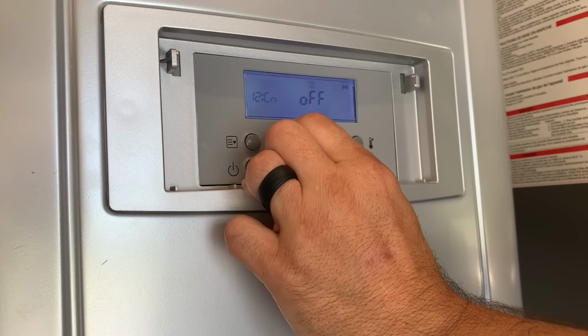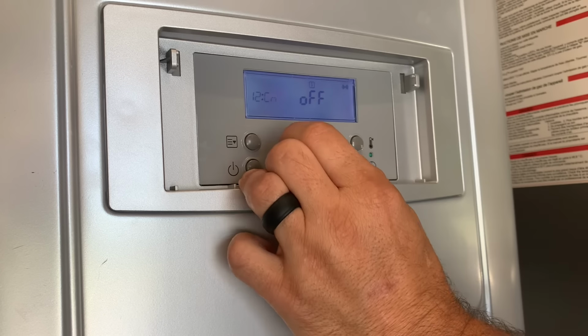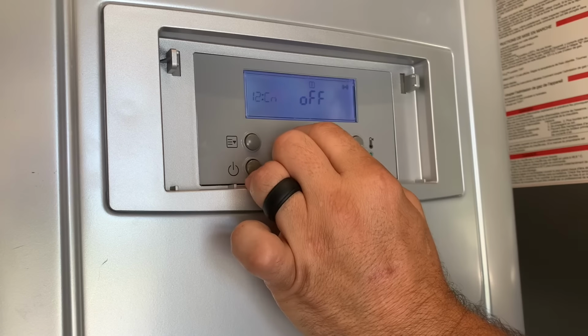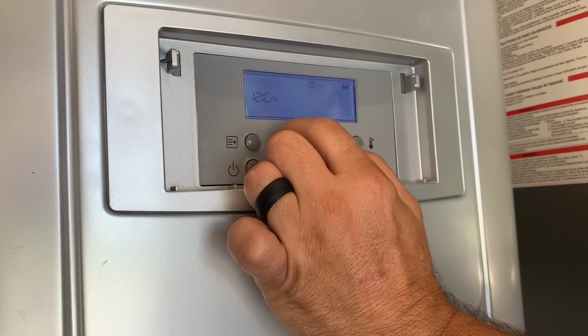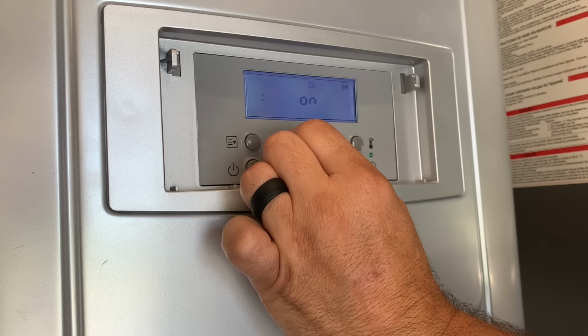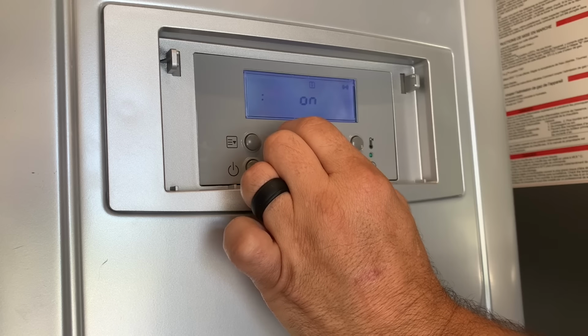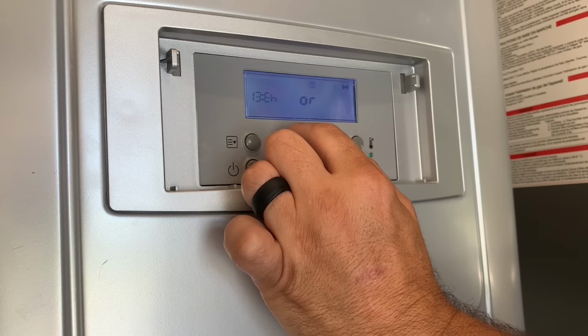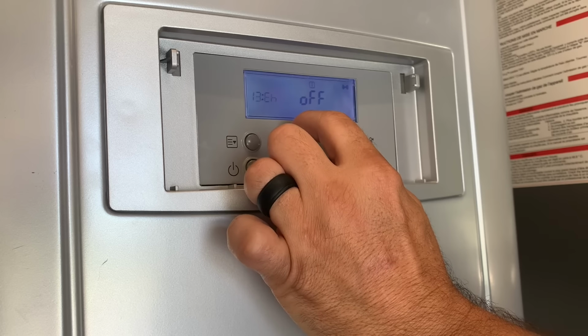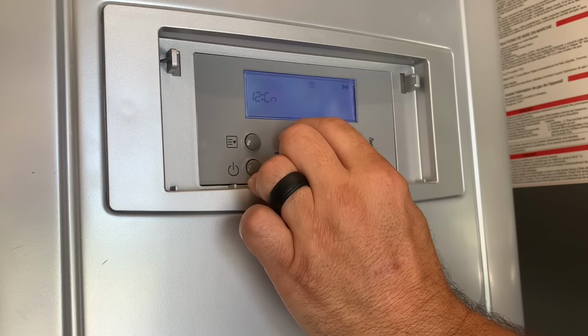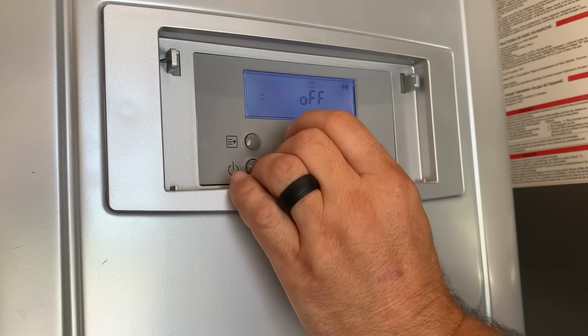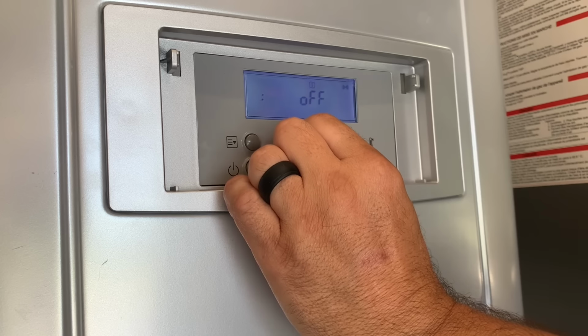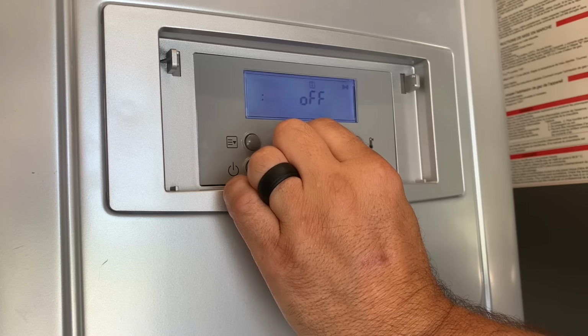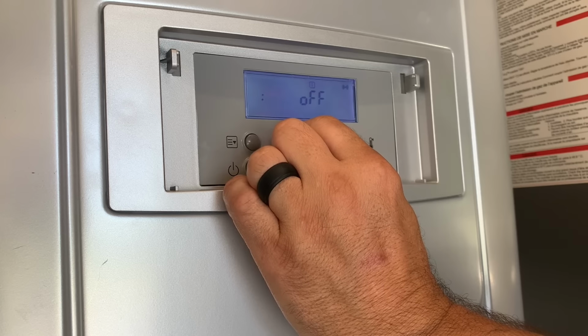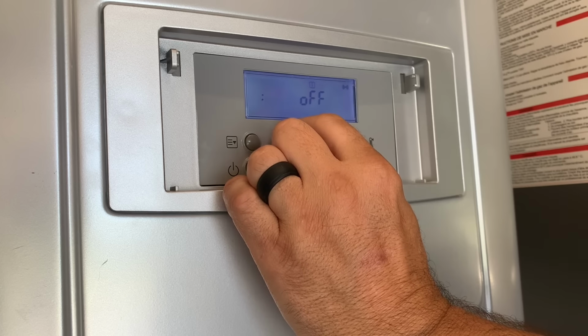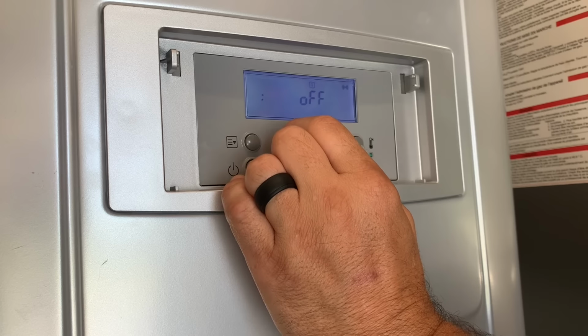All right. Now we're at 12 CN. That is Cascade, enables Cascade mode for multiple water heaters. Let's turn Cascade on so that we can access 13 EH for common venting. We can select that and let it know if we're common venting or not. We'll say no. And we're going to go back to 12 CN for Cascade. We do not use multiple units on this particular water heater, so we'll bypass that. 14 T1 test mode. Used to test the water heater when operating in internal recirculation mode only. And then 15 T2 is used to purge air from the water heater system with an external recirculation pump.